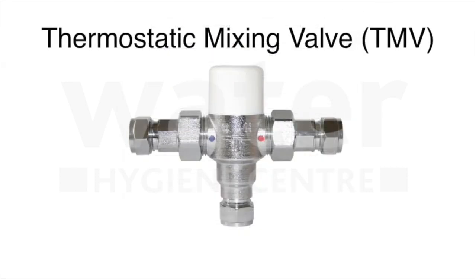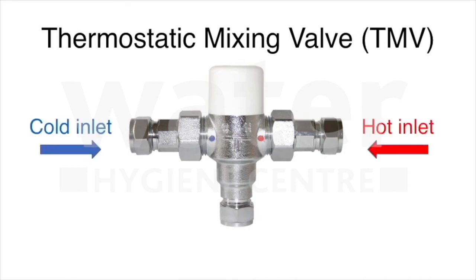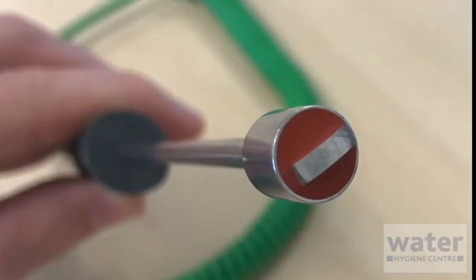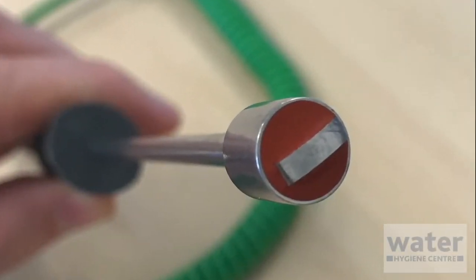Some outlets may have thermostatic mixing valves, commonly known as TMVs. A TMV is used to blend cold water and hot water to create a mixed supply at a preset temperature. This is usually used to prevent scalding. In order to get a true temperature, you must use a surface probe against the inlet supply pipes.